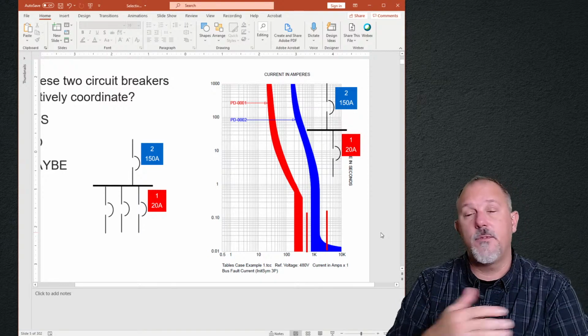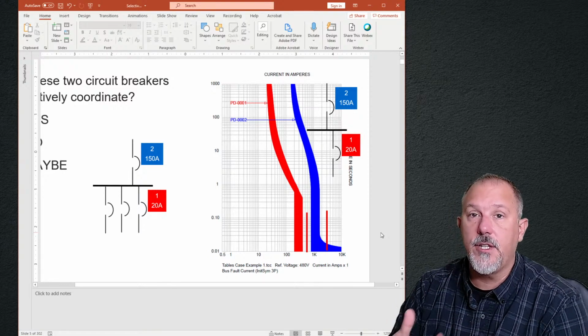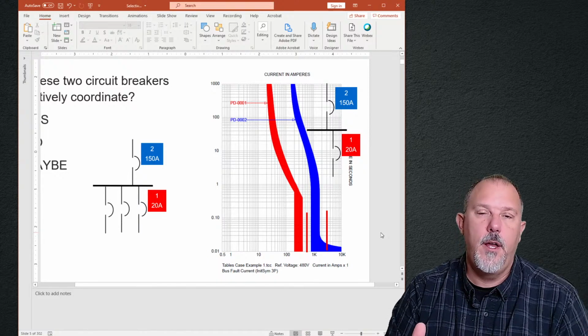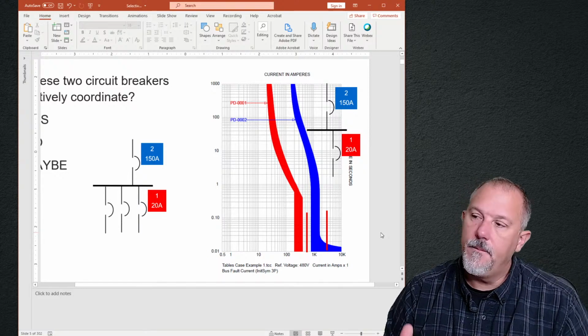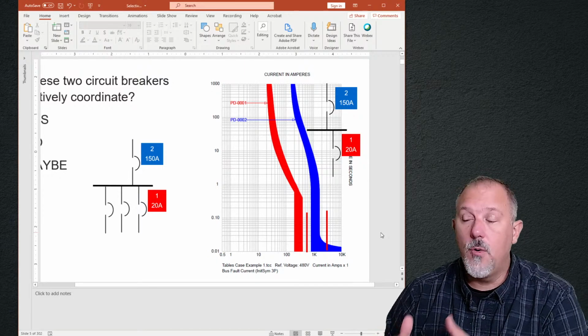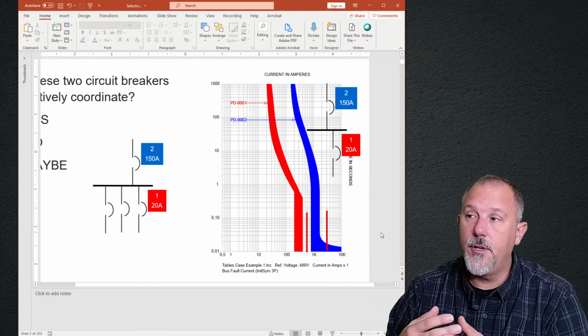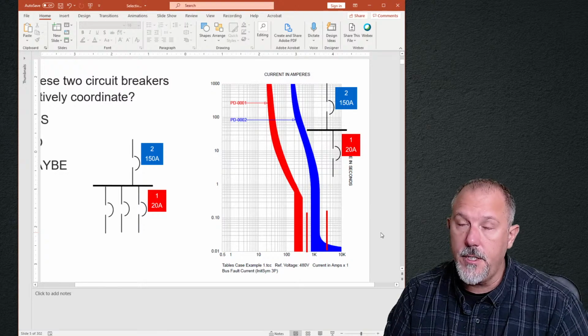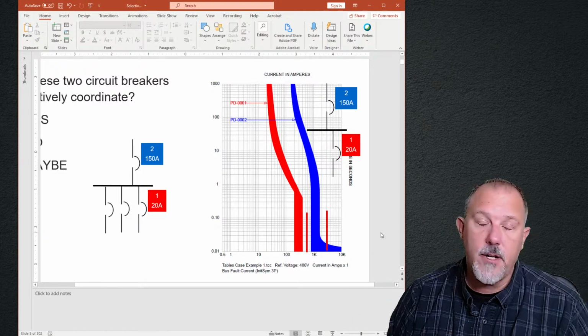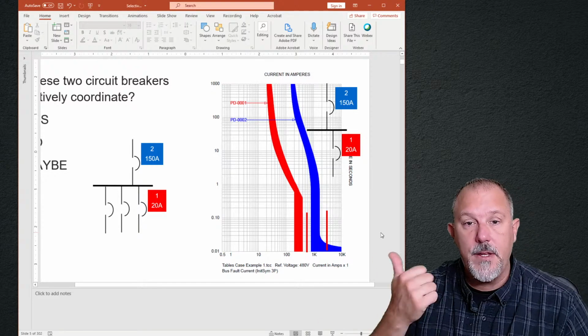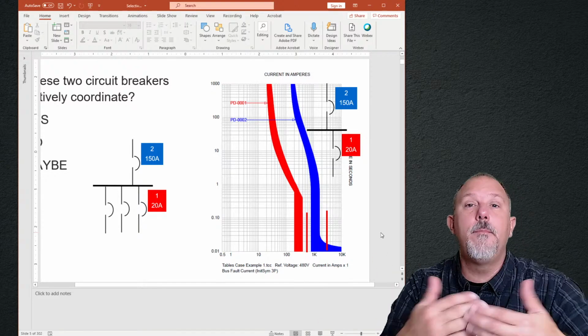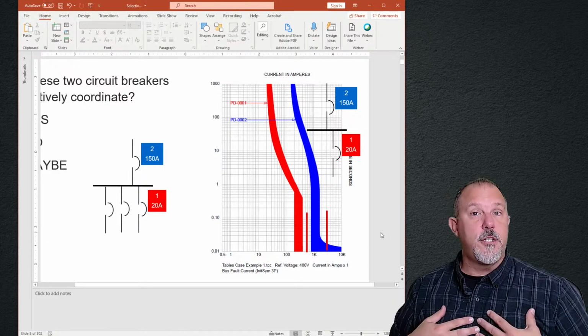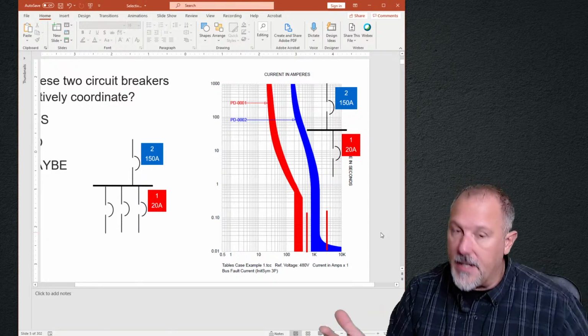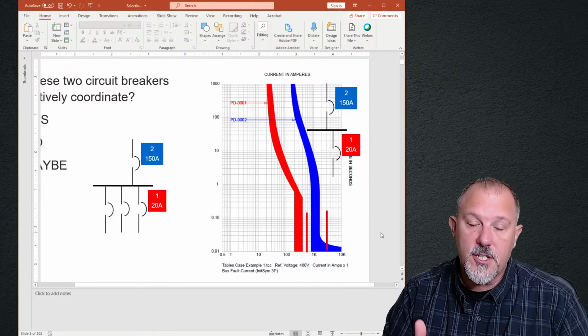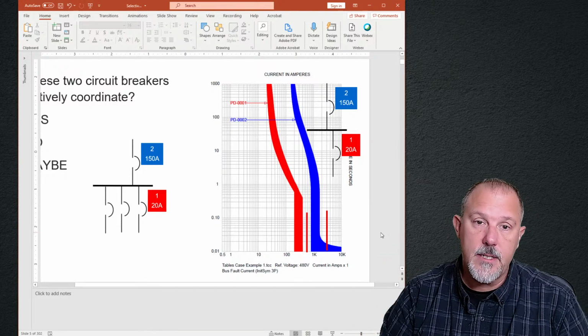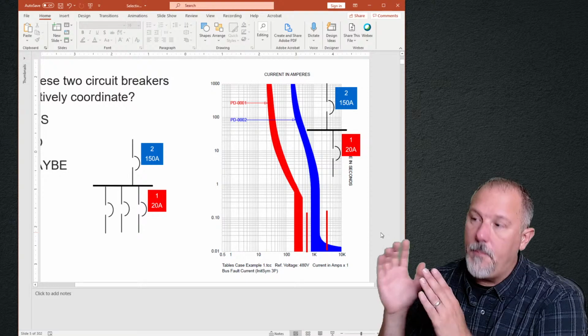And I would tell the customer, if you wanted to selectively coordinate so that you will never have the possibility of a cascading event, then I'd say you have to make a change. What are the possibilities? What would you do? I could add a transformer in to lower the fault current. I could increase the size of that 150 amp breaker to a larger breaker and move the instantaneous to the right. I would give the customer the options. I don't make the decision for the customer. I'm basically doing a study. If the customer said, I want a selectively coordinated system and I want you to design it that way, then I would pick different devices.